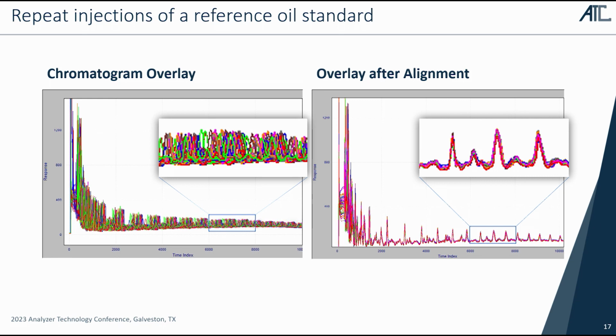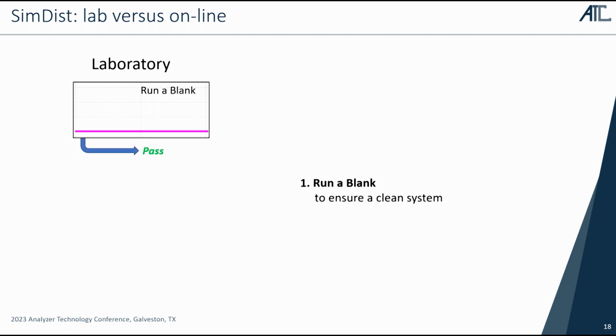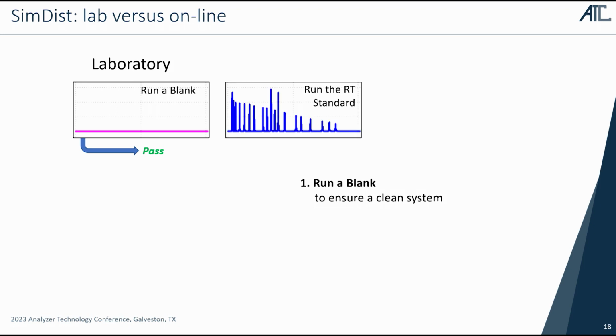Now, how do we use that? The primary places, at least in a refinery operation, will be detailed hydrocarbon analysis and simulated distillation. So let's look at an example with simulated distillation. If we're in the laboratory, what's the first thing you do with a chromatograph? You run a blank. Why do you run the blank? You want to make sure you have a clean system. The next thing you do is run a retention time standard.